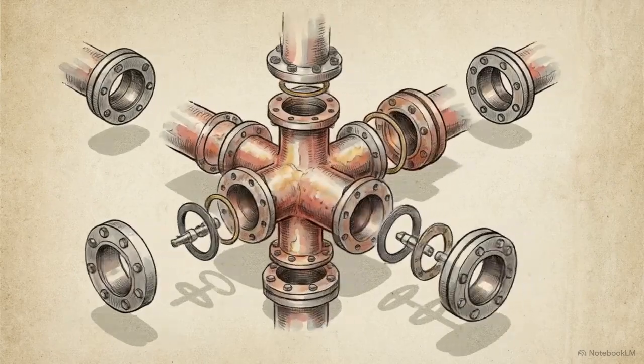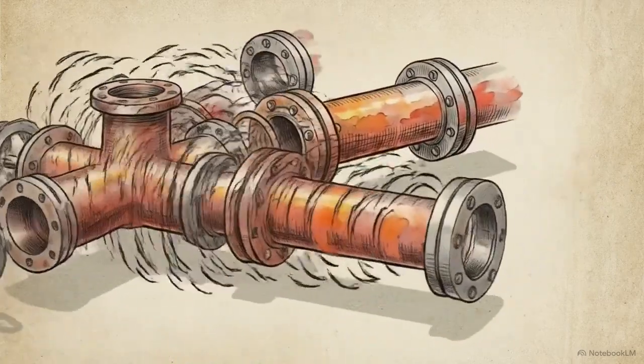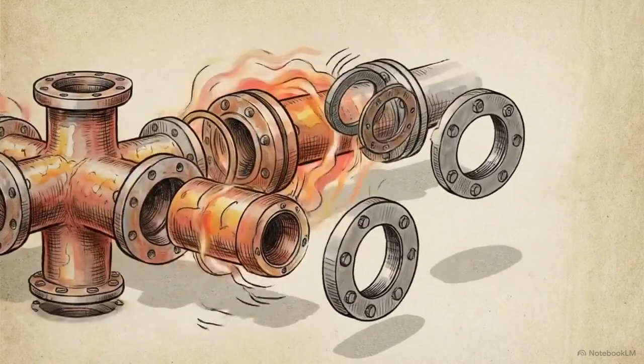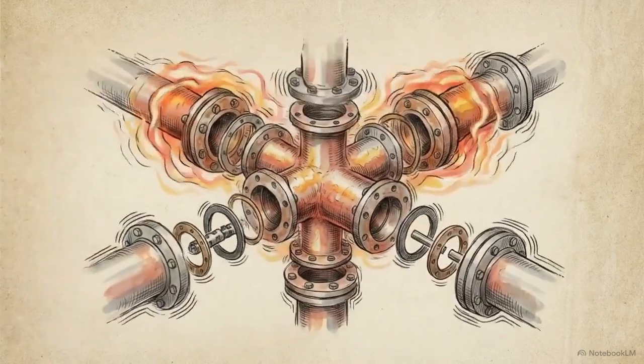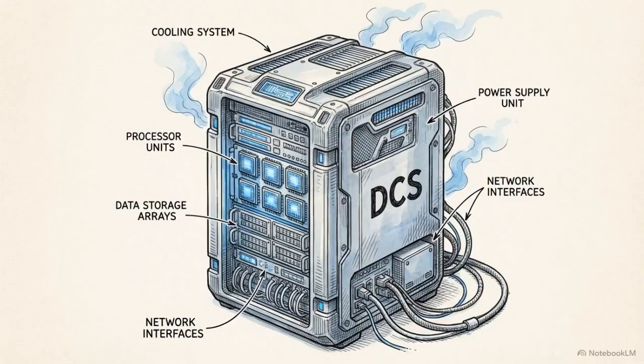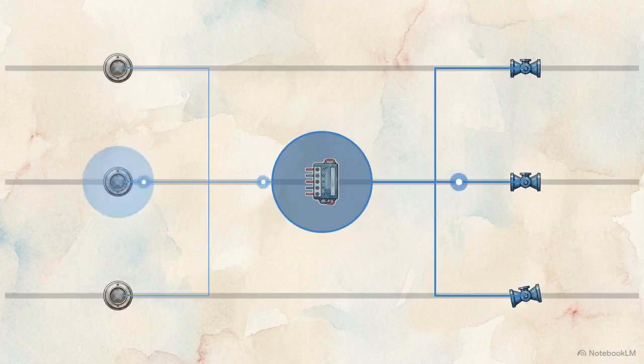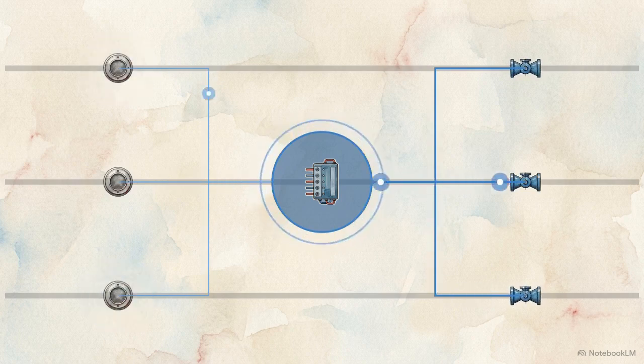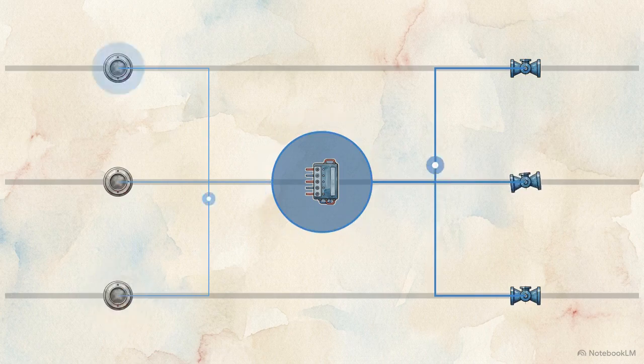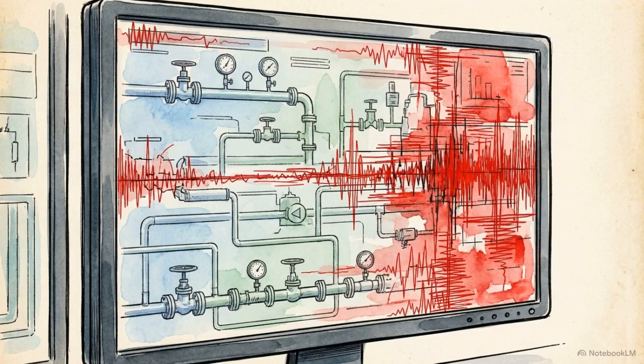Inside a modern industrial facility, highly volatile, pressurized fluids are kept in a state of continuous motion and extreme temperature. Keeping this volatile process stable requires a primary brain known as the Distributed Control System, or DCS. The DCS reads continuous data from sensors across the plant and executes real-time micro-adjustments to valves and pumps to keep production running smoothly. But any complex control system is vulnerable.